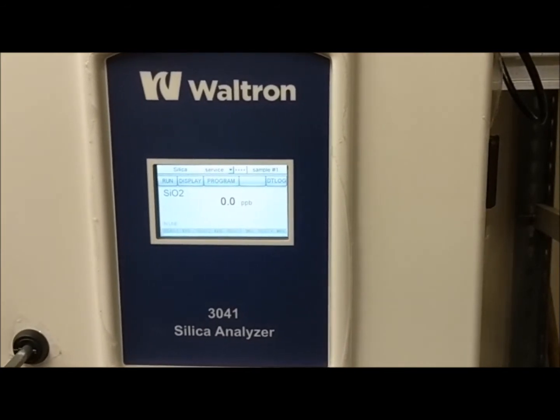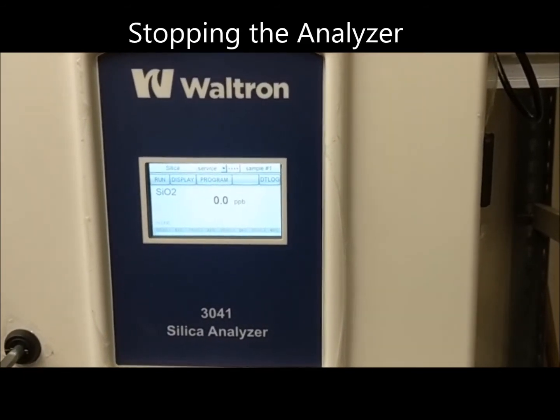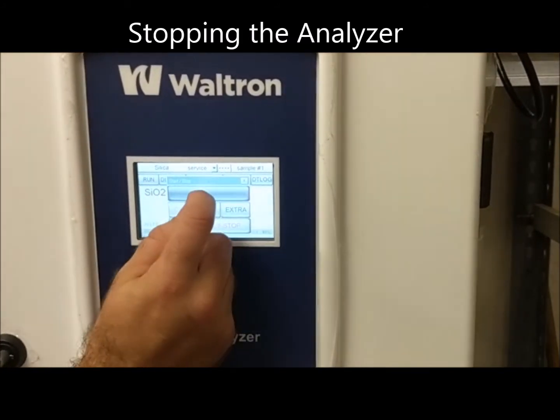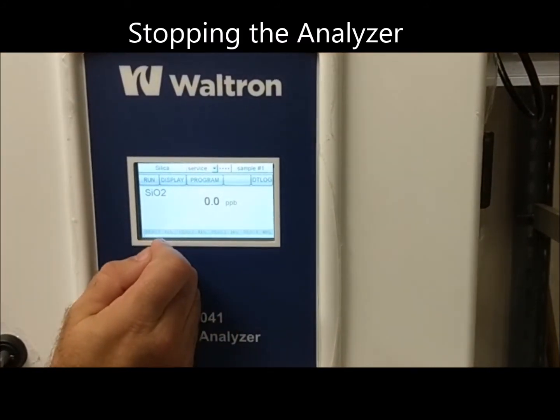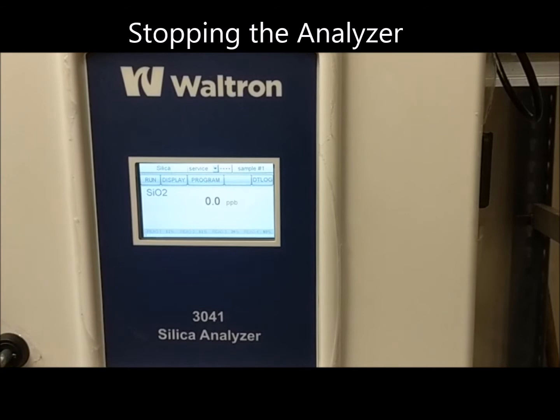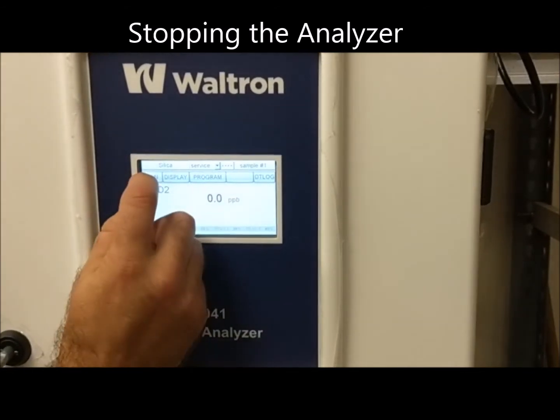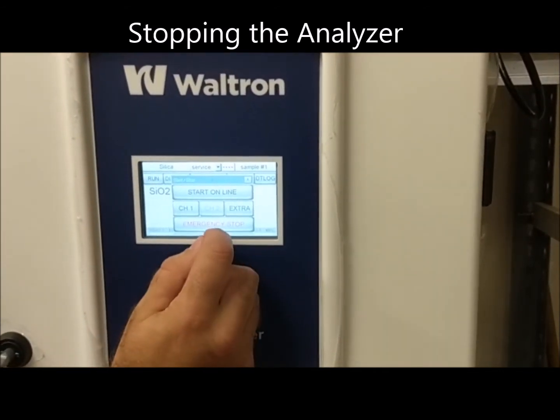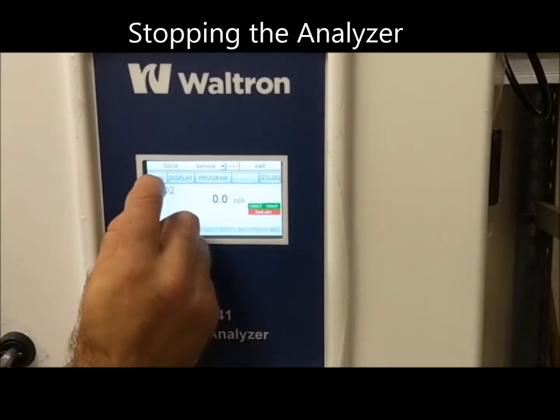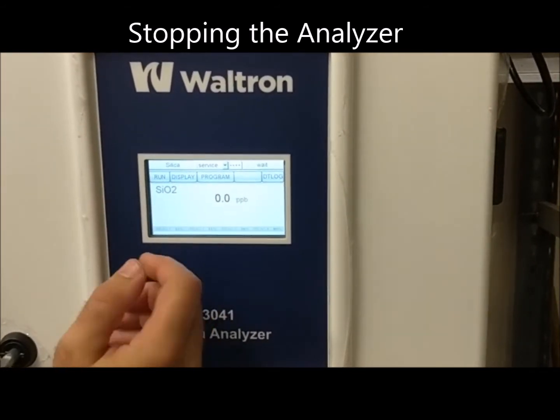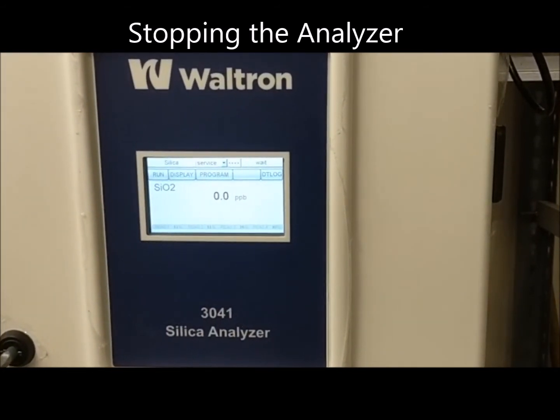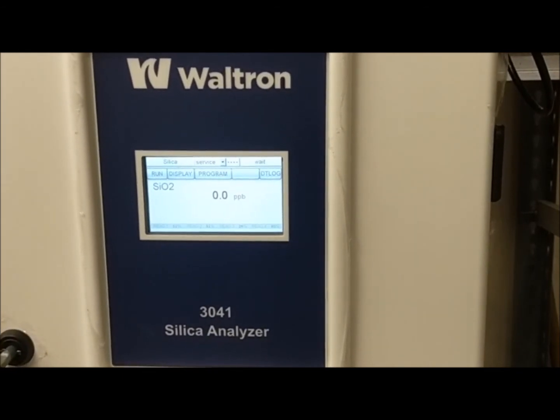not take any samples. In order to stop the analyzer in online mode, you can repress the button at the top, and that will allow the analyzer to complete the current analysis that it's on. If you need to stop immediately, you can press the emergency stop button and then the reset button to put the analyzer back into standby mode, and then either put it back online when ready or calibrate manually.